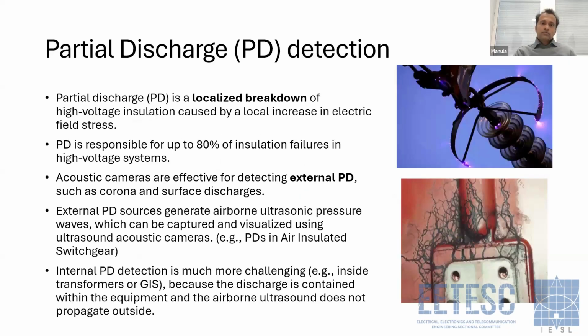Okay, so let's go to the applications. The first application of this kind of ultrasound camera is partial discharge detection, or we call it PD. What is a partial discharge? In high voltage systems, we have insulators. In these insulators, there might be localized discharges or localized breakdowns caused by a local increase in electric field stress.